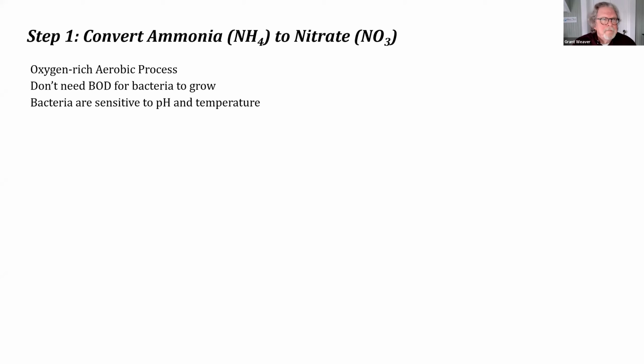Lucky you. So nitrogen removal is a 2-step process. Actually, it's more than that, but the organic nitrogen converts to ammonia without really any operator input. Not a lot of process control of converting organic nitrogen, maybe that's in urea and other compounds, to ammonia. The ammonia I write here is ammonium. For the geeks, NH4 versus NH3. It's the form that we usually see in wastewater, and the majority of ammonia is ammonium. You don't really need to know that.